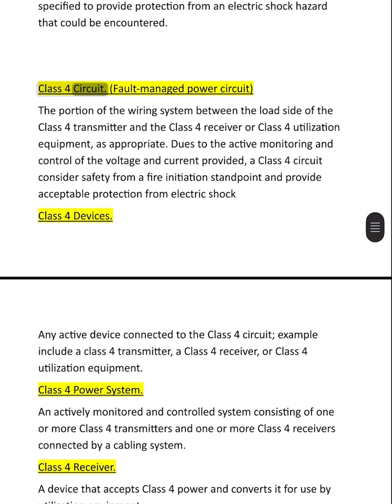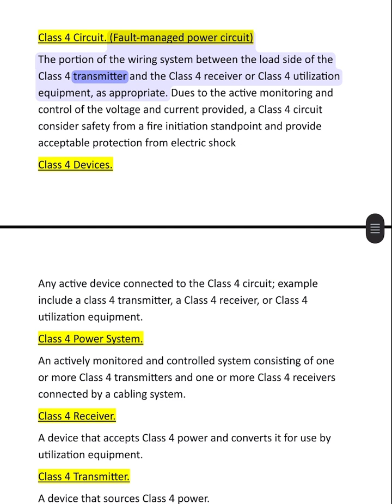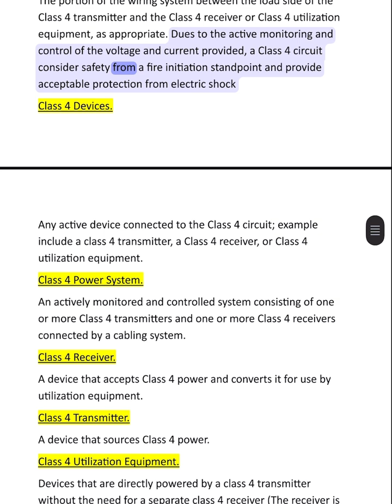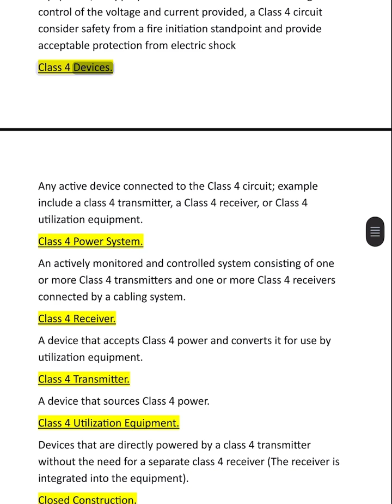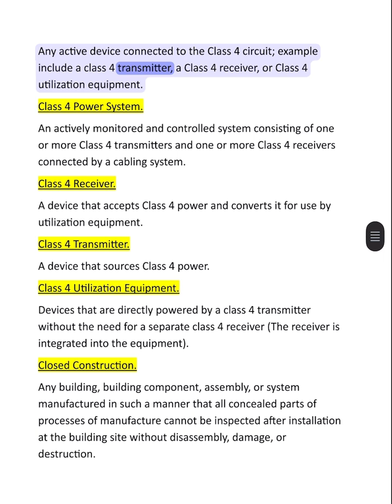Class 4 circuit, fault-managed power circuit. The portion of the wiring system between the load side of the Class 4 transmitter and the Class 4 receiver or Class 4 utilization equipment, as appropriate. Due to the active monitoring and control of the voltage and current provided, a Class 4 circuit considers safety from a fire initiation standpoint and provides acceptable protection from electric shock. Class 4 devices. Any active device connected to the Class 4 circuit. Examples include a Class 4 transmitter, a Class 4 receiver, or Class 4 utilization equipment.